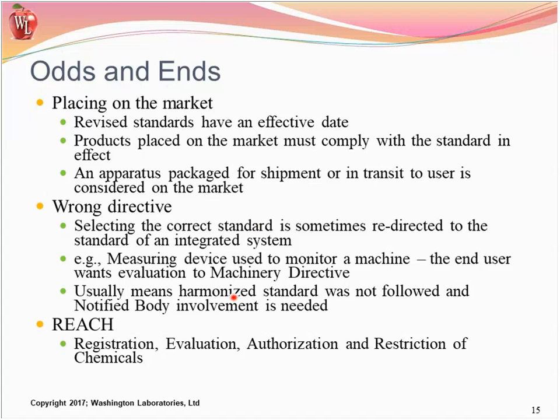So I may need to cite a wrong directive and apply a directive that's not obviously there. You can't declare compliance to directives without the evaluation to those. If I have measurement equipment, that's not the same as IT equipment, so I may need to take care of the product standard. Measuring devices, sometimes monitoring machines, etc., so machinery may get involved. It usually means a harmonized standard is not followed and a notified body involvement tends to be necessary. So I may qualify the laptop with CE marking on it as information equipment, and if I want to apply it differently, then I need to get a notified body involvement or evaluate to the harmonized standard you want to declare.